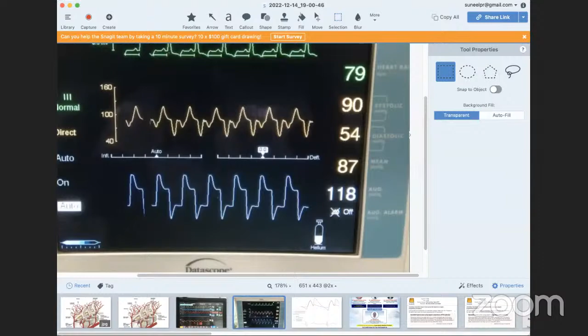There is a minimum augmentation and a maximum augmentation, which is the amount of helium that fills the balloon. So even with that, we can start weaning IABP. One more thing to keep in mind during the weaning process: if you're putting the IABP on standby and seeing if the patient's hemodynamics are well maintained just with inotropes and pharmacotherapy, we have to be careful not to keep the IABP on standby for more than 30 minutes. It's not recommended. So once weaning is done, say 1:3 frequency, or the augmentation is also completely reduced and the patient is tolerating this, the IABP can be put on standby mode and removed.